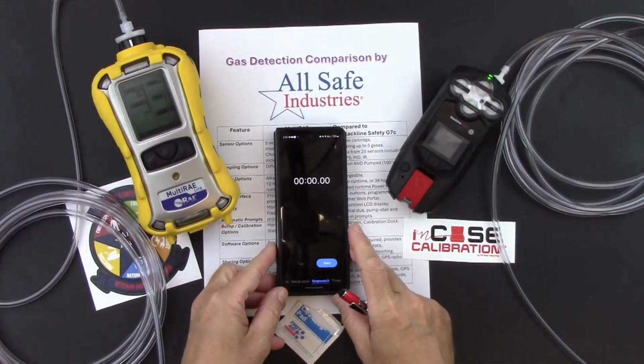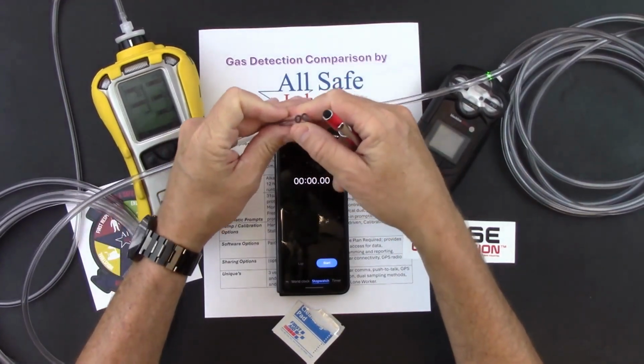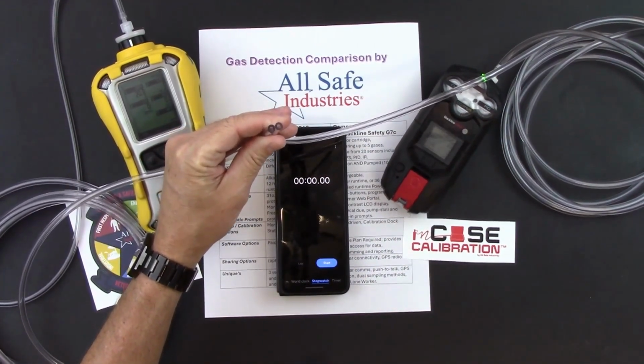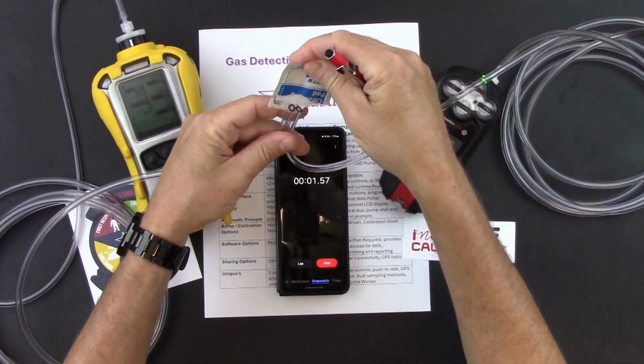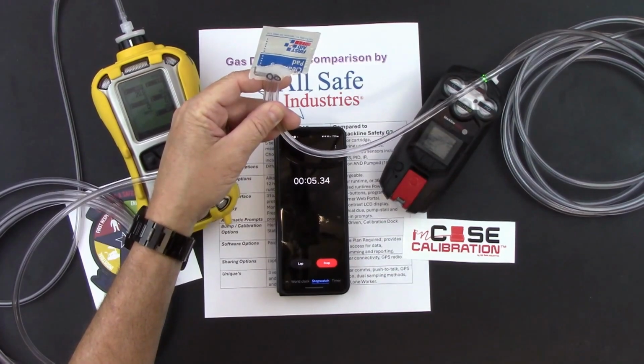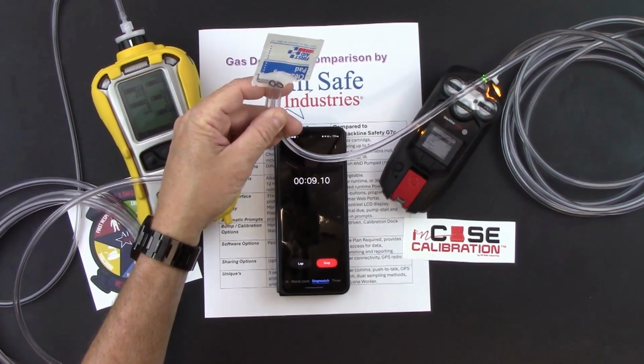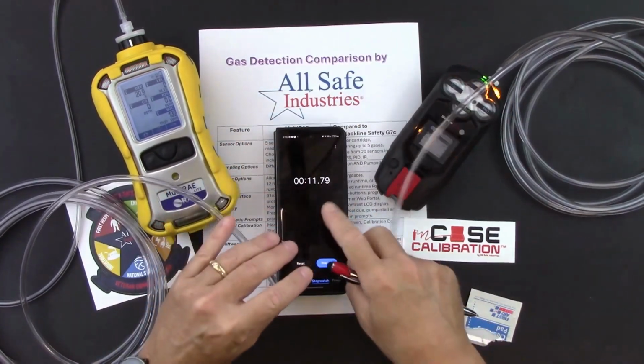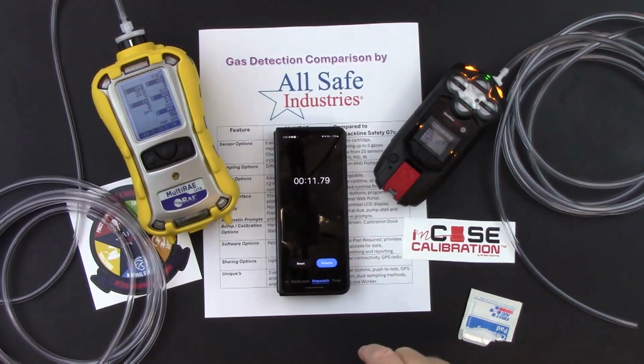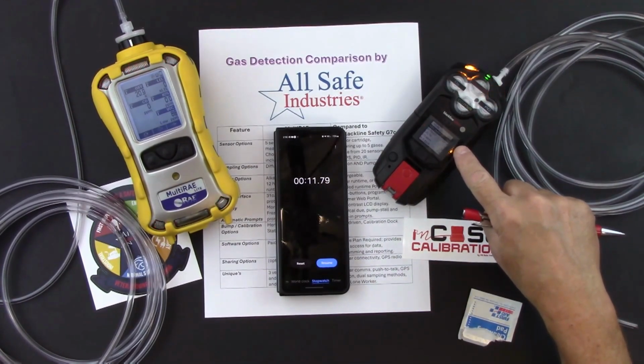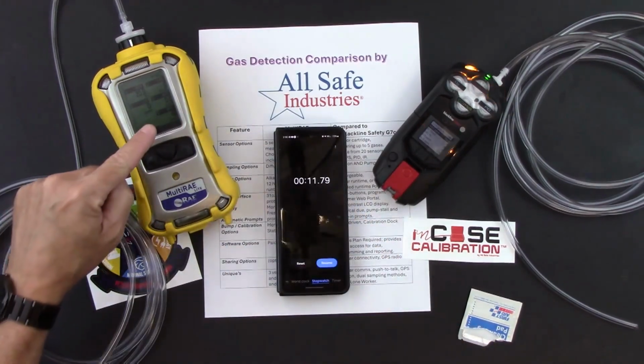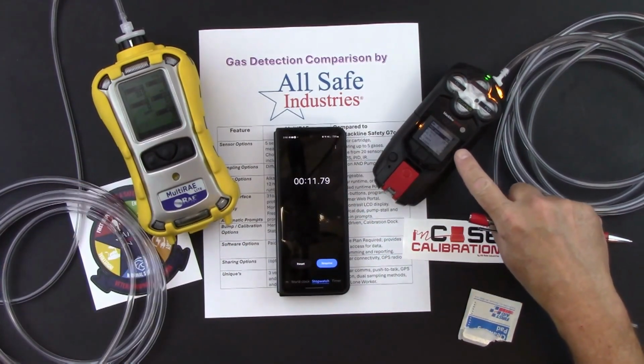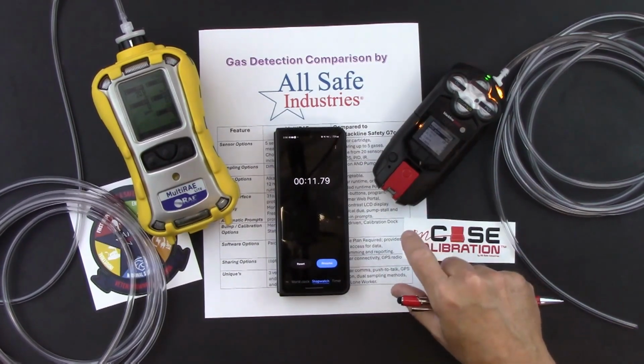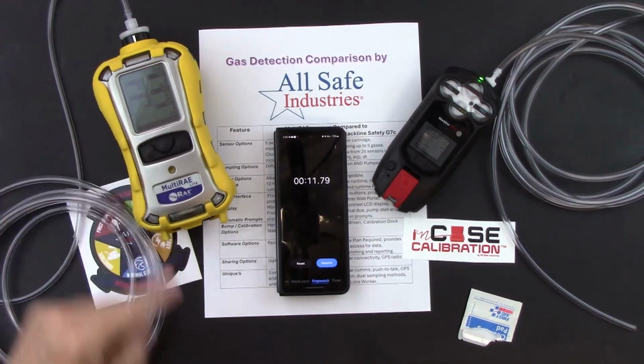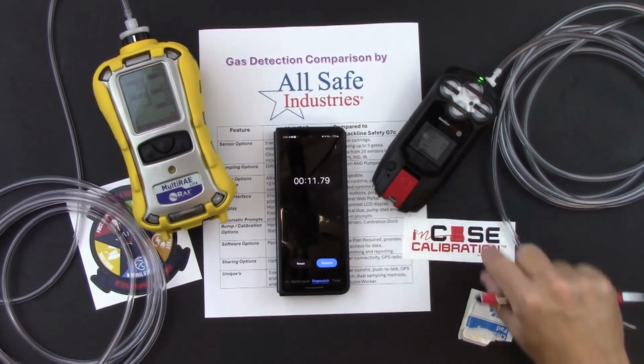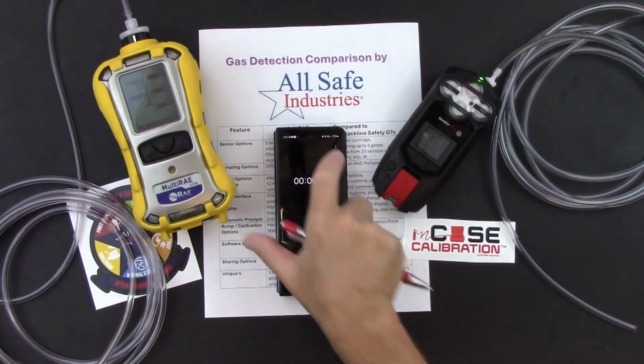I'm going to bring in my stopwatch here to time the response time, grab both ends of the tubing. Then I'm going to take my alcohol wipe and hit start. And then watch the readings on the instruments. Both of those went into alarm right about the same time. Got into the 200s over here, got into the hundreds over here. I've already recovered on my MultiRAE, and I'm just about recovered on my G7c. You can see my MultiRAE has nearly recovered to 0, and my G7c is on the way down to 0 itself. So good response time on both instruments.